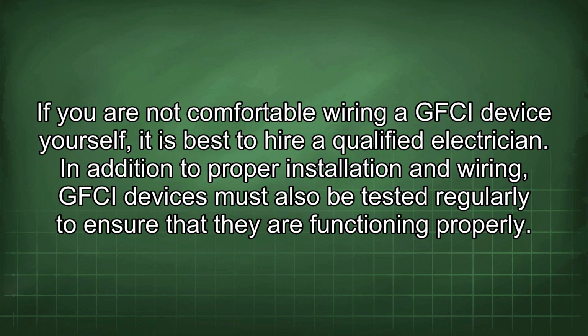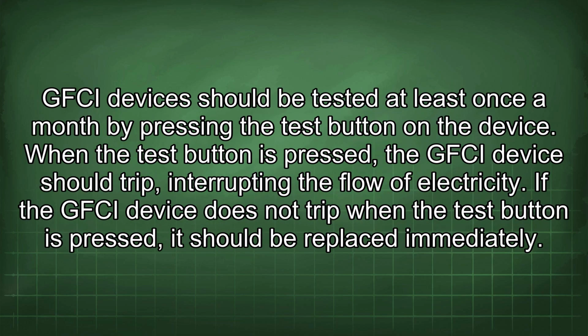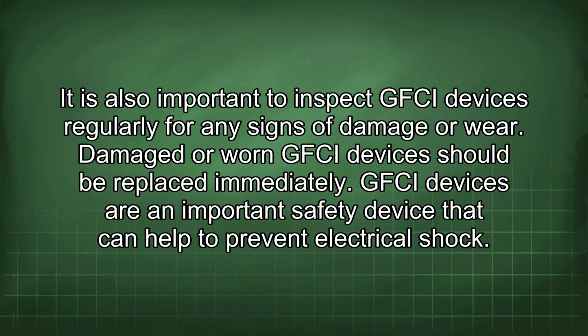In addition to proper installation and wiring, GFCI devices must also be tested regularly to ensure that they are functioning properly. GFCI devices should be tested at least once a month by pressing the test button on the device. When the test button is pressed, the GFCI device should trip, interrupting the flow of electricity. If the GFCI device does not trip when the test button is pressed, it should be replaced immediately. It is also important to inspect GFCI devices regularly for any signs of damage or wear. Damaged or worn GFCI devices should be replaced immediately.